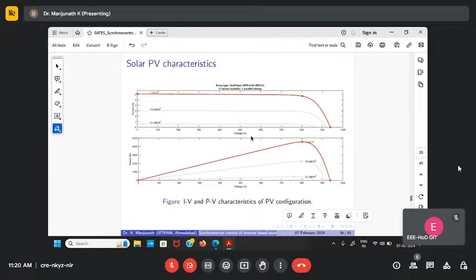The actual power delivered by the inverter has some transient in the beginning, but after some time the actual power and PV power start tracking. After 5 seconds it is almost the same. The reason for this transient is the control values, or improper design of control parameters of the frequency control loop or the DC link voltage control loop.